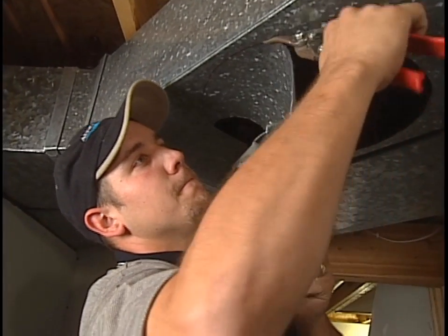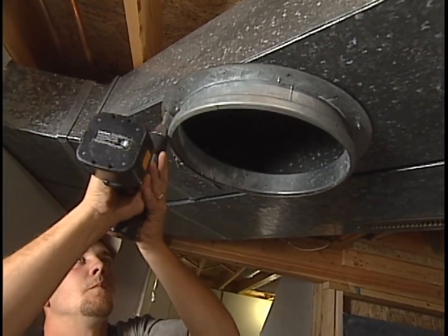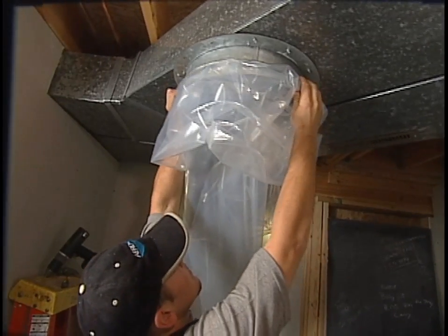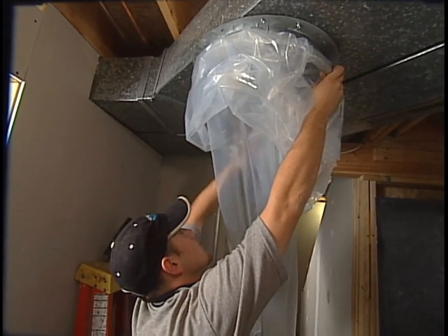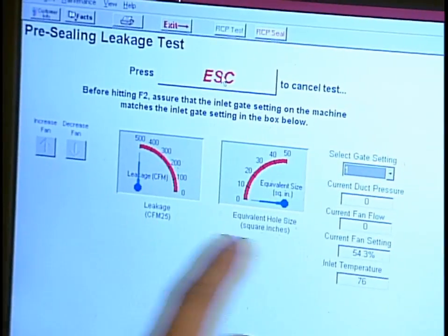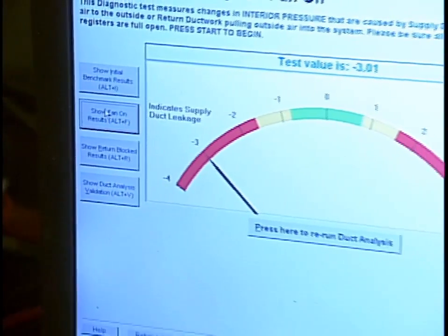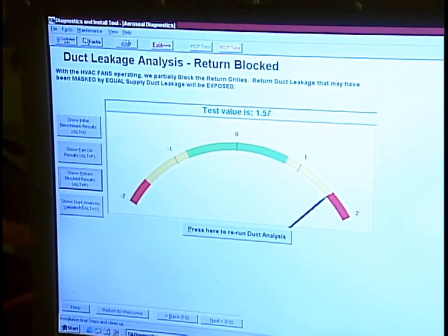What's the first step? Walk me through step by step. They come out to the house and cut a hole in basically one of the plenums in your duct system, which is one of the larger ducts. They connect a big plastic bag that connects to the machine that creates the aerosol particles. They then block all of the registers, turn on the machine, and inject those particles over time. The process is tracked by a computer — it's all set up to run with a laptop. Minute by minute, you get a graph showing the leakage in your duct system going down. At the end, they take one final test and you get a report showing where you started, the process you went through, and the final result.